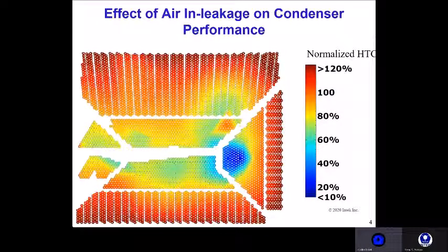As you can see, in the area near the mouth of the air removal section, there's quite a bit of yellow and green areas representing 60 to 80% cleanliness factor. This is the stagnant zone area on this tube bundle design. The stagnant zone you can see stretch over to the right and connects to this blue pocket of tubes, which has approximately 25% cleanliness factor.